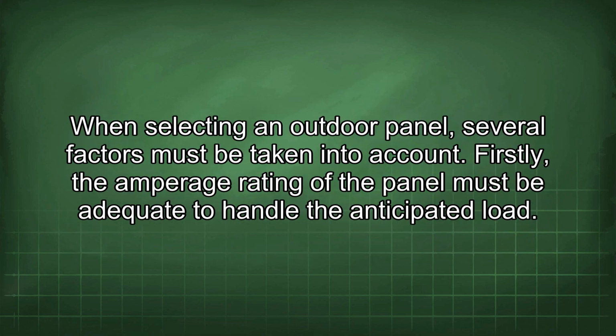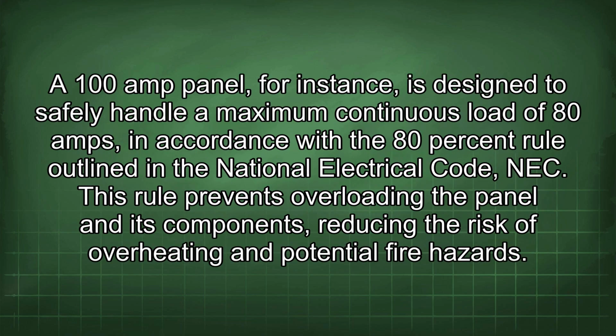When selecting an outdoor panel, several factors must be taken into account. Firstly, the amperage rating of the panel must be adequate to handle the anticipated load. A 100 amp panel, for instance, is designed to safely handle a maximum continuous load of 80 amps, in accordance with the 80% rule outlined in the National Electrical Code (NEC). This rule prevents overloading the panel and its components, reducing the risk of overheating and potential fire hazards.